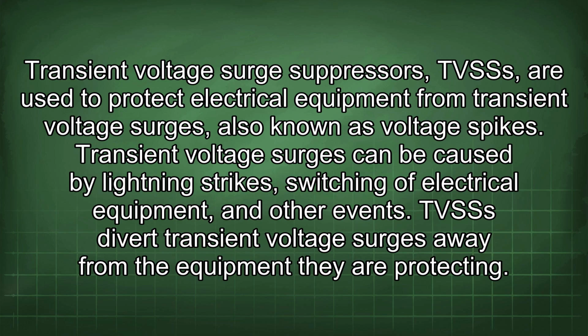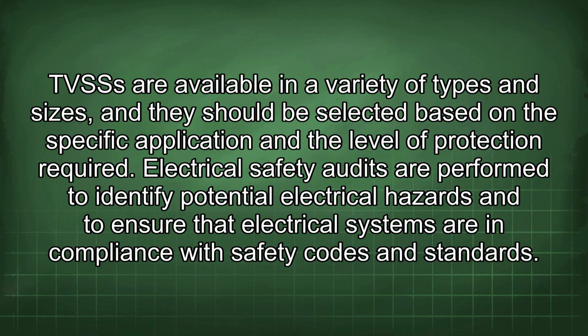Transient voltage surge suppressors (TVSSs) are used to protect electrical equipment from transient voltage surges, also known as voltage spikes. Transient voltage surges can be caused by lightning strikes, switching of electrical equipment, and other events. TVSSs divert transient voltage surges away from the equipment they are protecting. TVSSs are available in a variety of types and sizes, and they should be selected based on the specific application and the level of protection required.